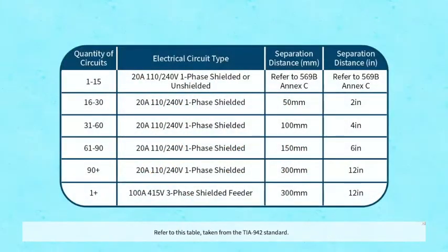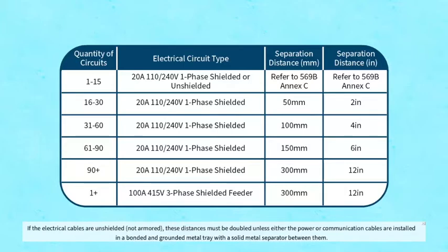Refer to this table taken from the TIA 942 standard. If the electrical cables are unshielded and not armored, these distances must be doubled unless either the power or communication cables are installed in a bonded and grounded metal tray with a solid metal separator between them.